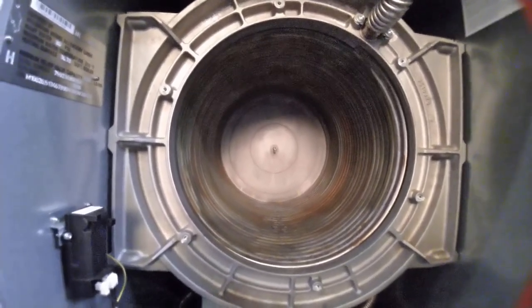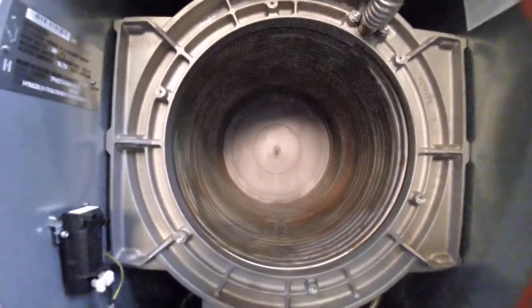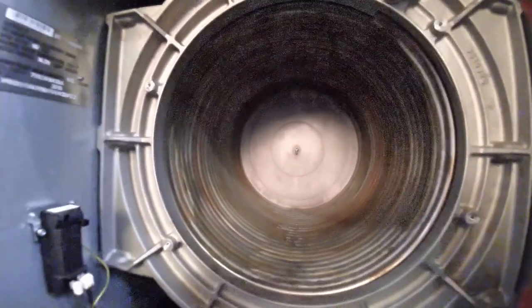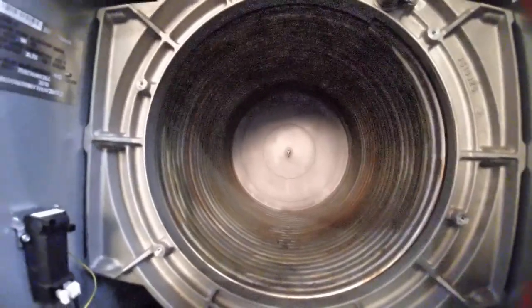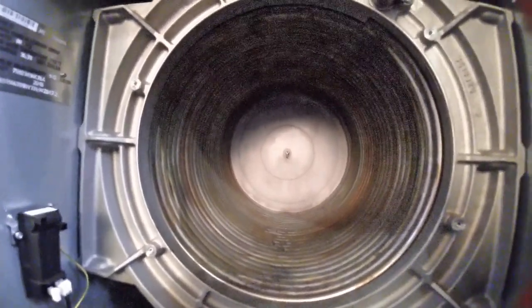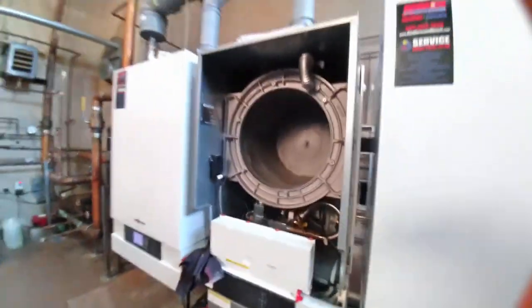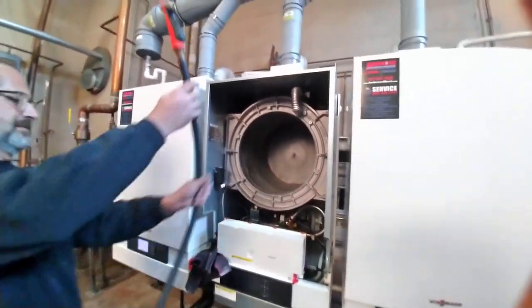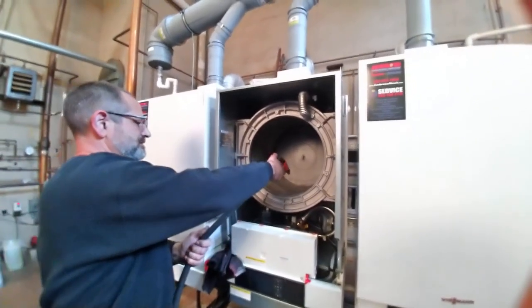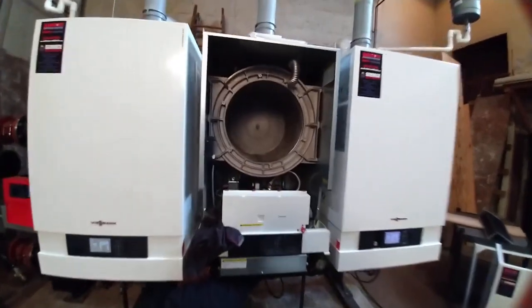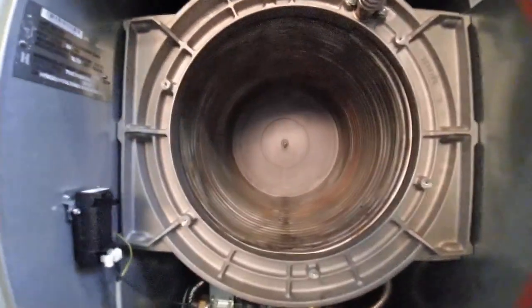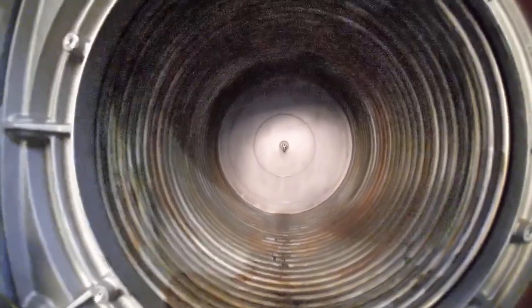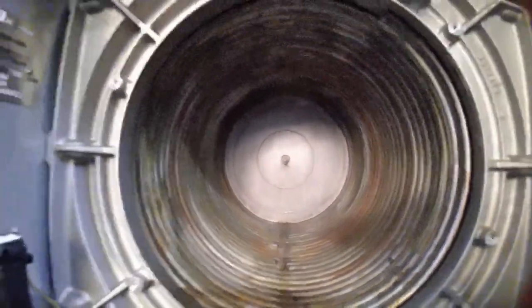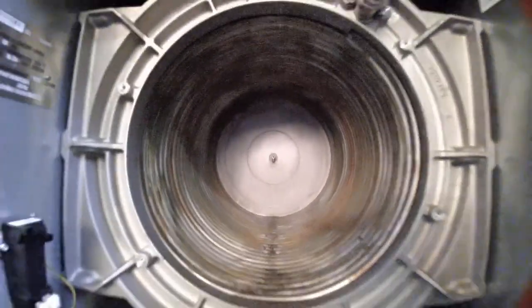Most manufacturers don't really recommend that you clean them with anything but hot water, and if they do allow something, it's probably going to be a citrus-based cleaner. Only use what the manufacturer recommends. So we're going to hose this one out to finish the cleanup before we reassemble it. After hosing it down, we're going to give it a minute or two to dry out. We're also going to wipe it down. We want to wipe the back plate. We don't want to reinstall that refractory on a wet back plate, get it wet and possibly damage it.